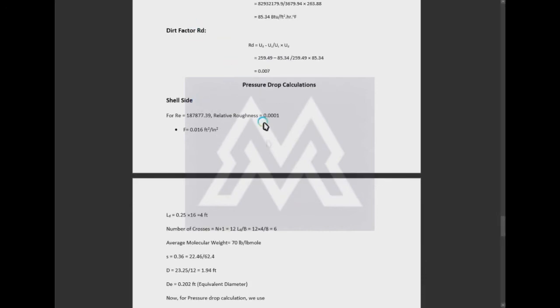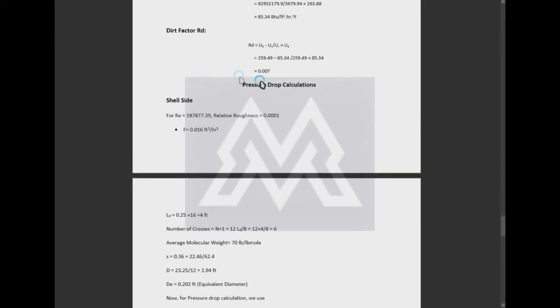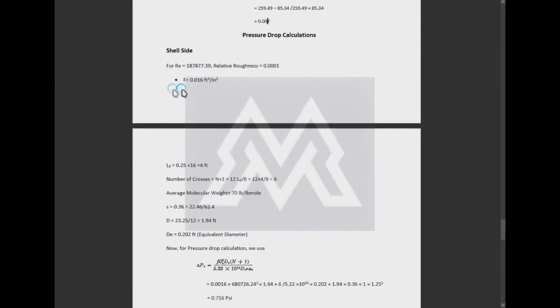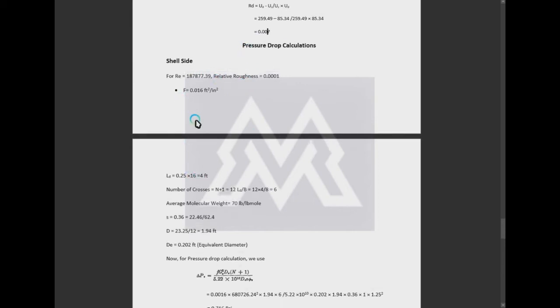The last step is the pressure drop calculation. Now it can be done in two ways. One is by using the formulas of fluid mechanics, where you can distribute the pressure drop into drag force or skin friction factor, or both. But the problem is the heat transfer geometry is not sustained in those calculations. For heat transfer calculations, you have to use the pressure drop formulas defined in chapter number 6 of Process Heat Transfer by D.Q. Kern.